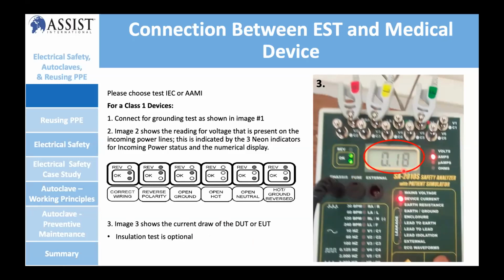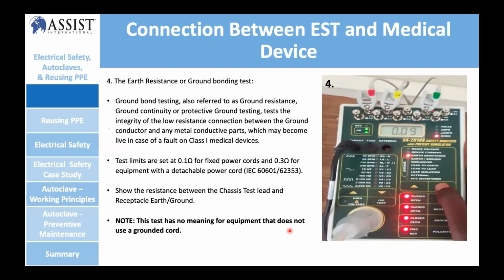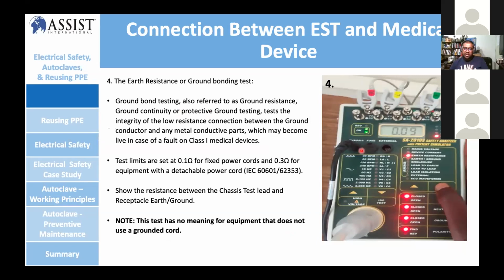So you're measuring device current, and after you measure the device current, you have to measure the resistance between the ground from the power cord to your patient monitor. So the earth resistance, ground bonding, the reading is somewhere around 0.09, and the normal limit should be somewhere from 0.1 to 0.3 for a detachable power cord according to IEC 60601 and 62353. This is the international standard. And resistance between chassis, test lead, and the earth line. So this is how it's done.